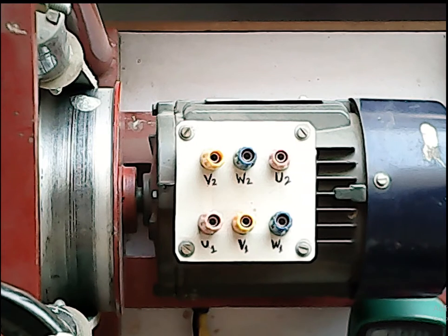So first we will be connecting the motor in star configuration. Another thing that we should know is that we are feeding the motor through an auto transformer, where we are trying to maintain a 220 volt phase to neutral supply. Now let us see how we are going to make the star connection. The star connection can be of 3-wire type and 4-wire type. Here we will be using a 4-wire connection, where the 3 phase lines will come from the auto transformer output, and there will be a neutral connection as well.